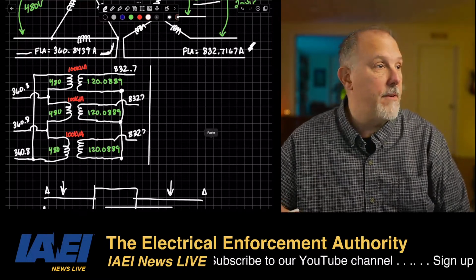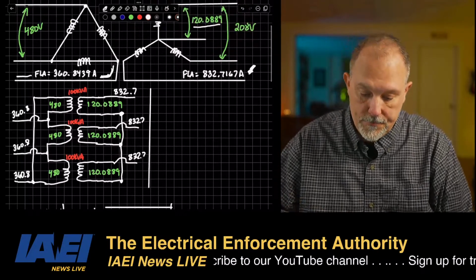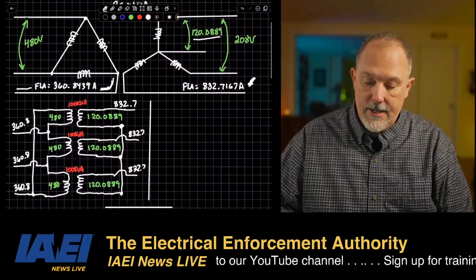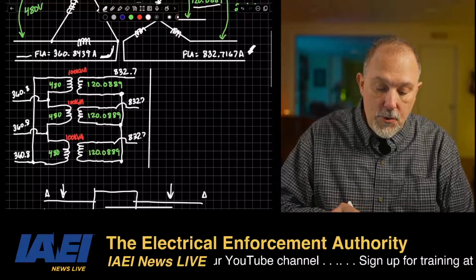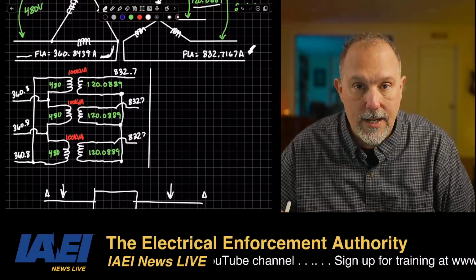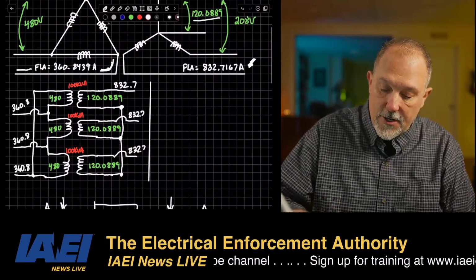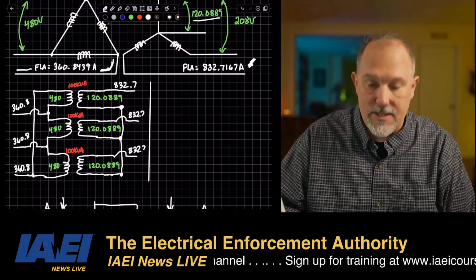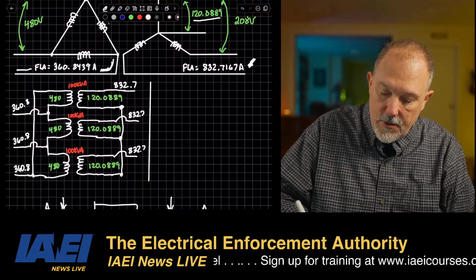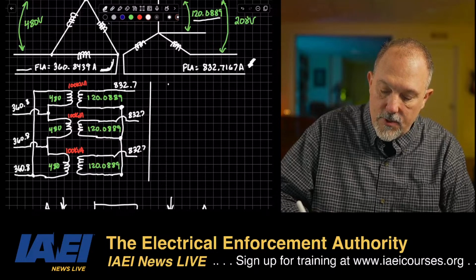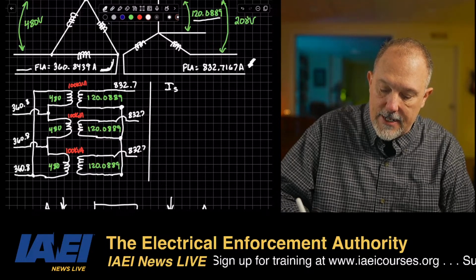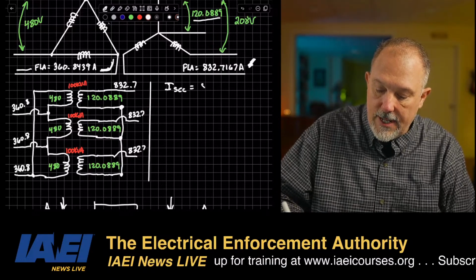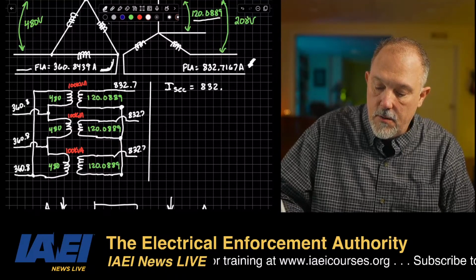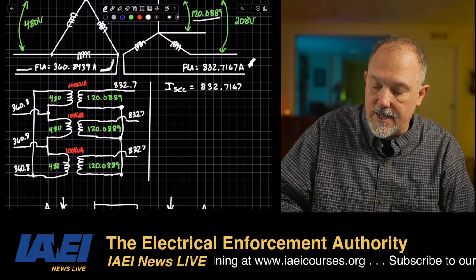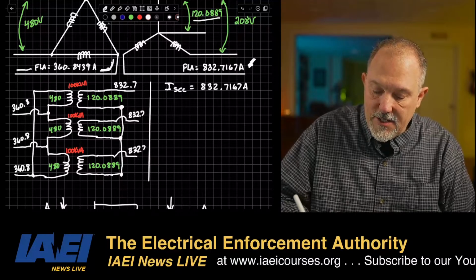If I'm going to use the 480 to 120, now we know the secondary current, full load amps, we'll call this I secondary, is equal to 832.7167 amps.